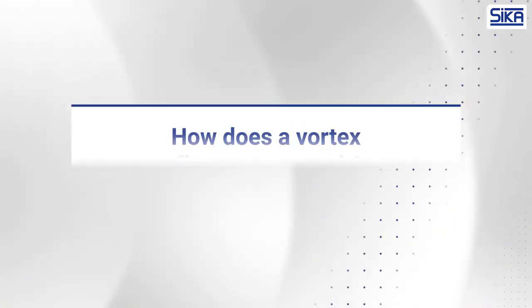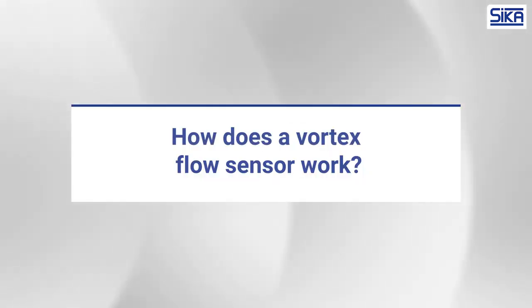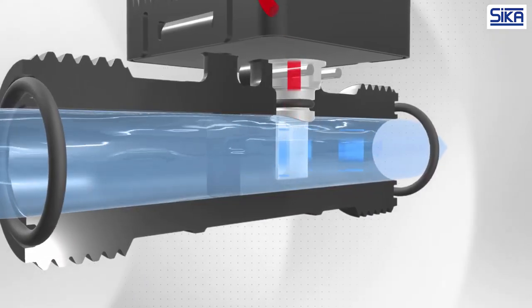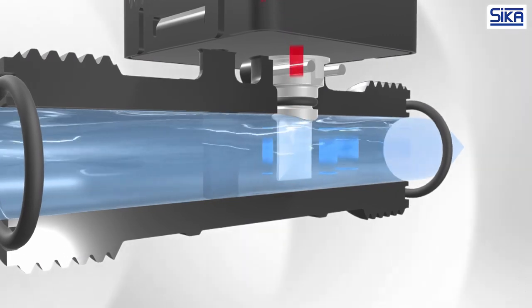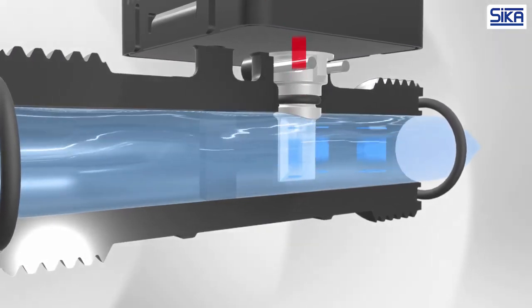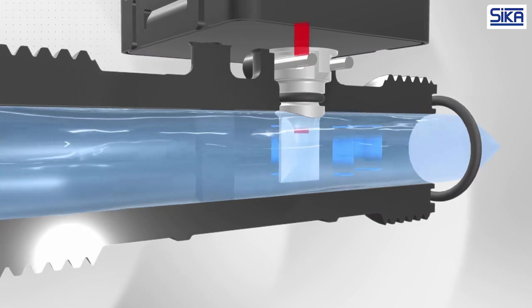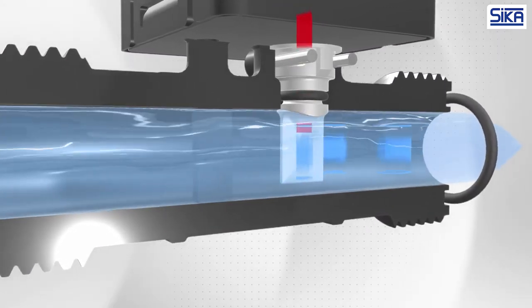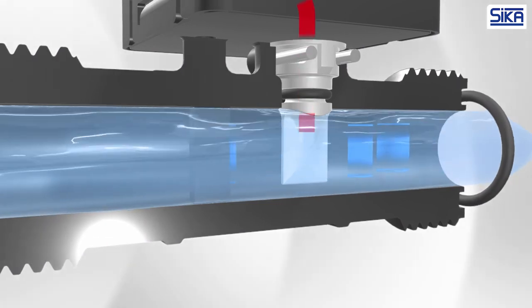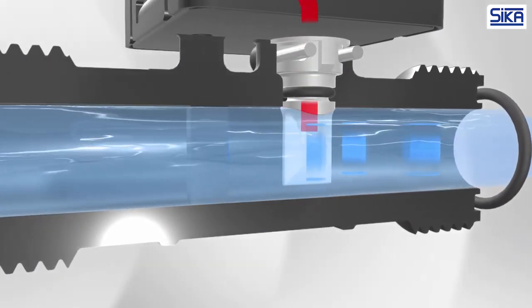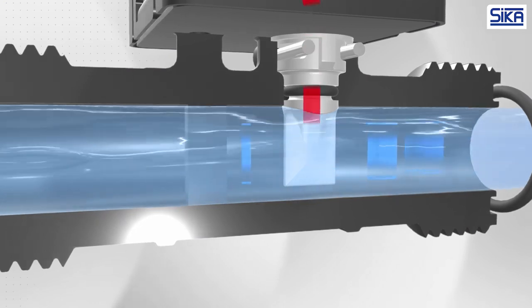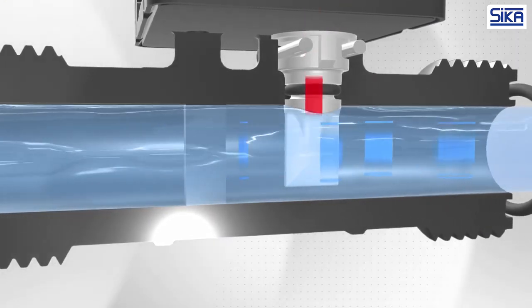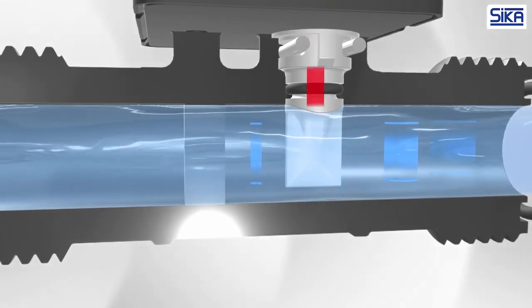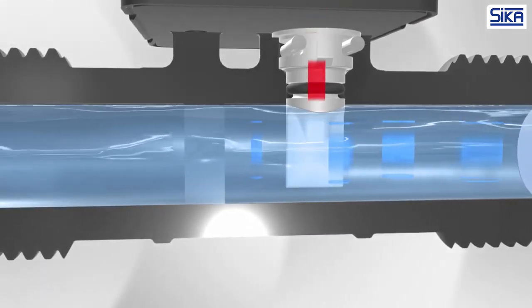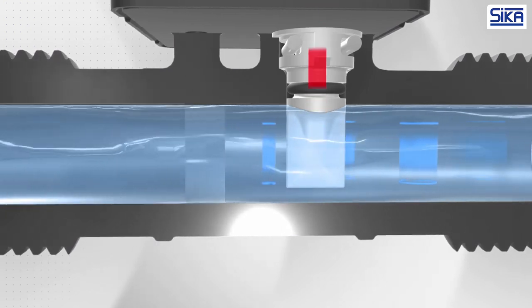How does a vortex flow sensor work? Let's take a closer look at the measurement principle. When fluid flows around a bluff body, a repeating pattern of alternating, offset vortices is created downstream of the bluff body. The vortices separate at the edges of the bluff body and create a Kármán vortex street in the flow. The distance between the individual vortices is constant. The frequency at which the vortices flow past a sensor depends on the flow velocity and is proportional to the flow rate. The sensor detects the vortices, which are converted into an electrical frequency signal.